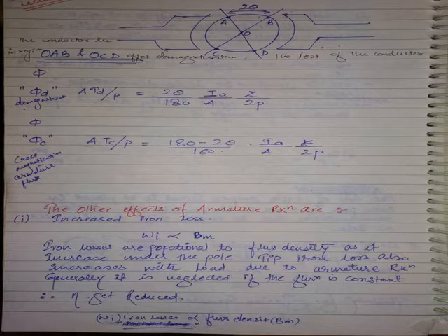When this varying flux, small variations, are there in the yoke and in the pole core, automatically it links with them, and what will it produce again? Voltage and eddy currents. That's why, to eliminate them, in all the recent machines the yoke as well as pole cores are also laminated.